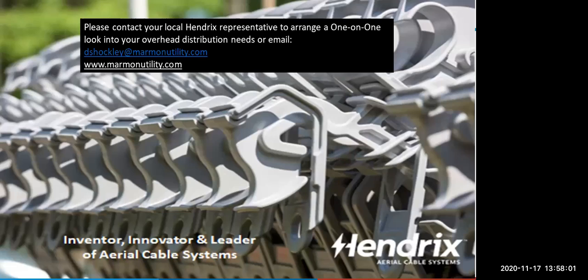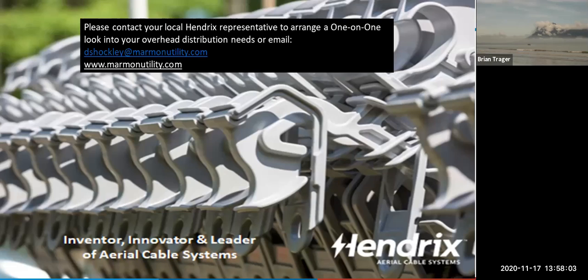Yes. Okay, so Sicame came out years ago with their IPCs, insulation piercing connectors. Our company went to France to witness the type test for them. We set up a very rigorous schedule of type tests, and Sicame spent a king's ransom getting all these type tests done, and I believe they are approved for 15 kV up to a certain size based on US, ANSI, and ICEA standards.